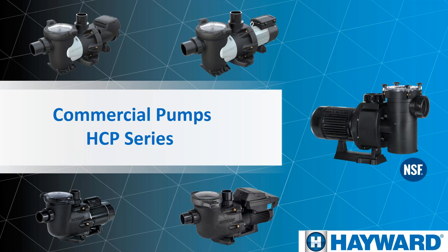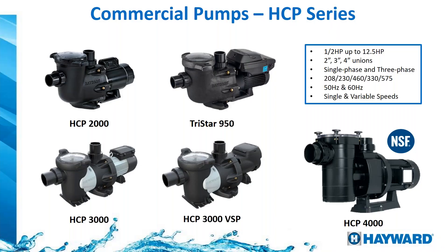Let's talk about commercial pumps — this is going to be the HCP series. We have several models: the HCP-2000, the TriStar 950, the HCP-3000 also in variable speed, and the biggest one is the HCP-4000, which goes up to 12.5 horsepower. Connections on these models vary from 2-inch or 2.5-inch up to 4-inch. Depending on the model and size of the pump, connections can be 208 or 230 volts, up to 460, 330, or 575 volts.